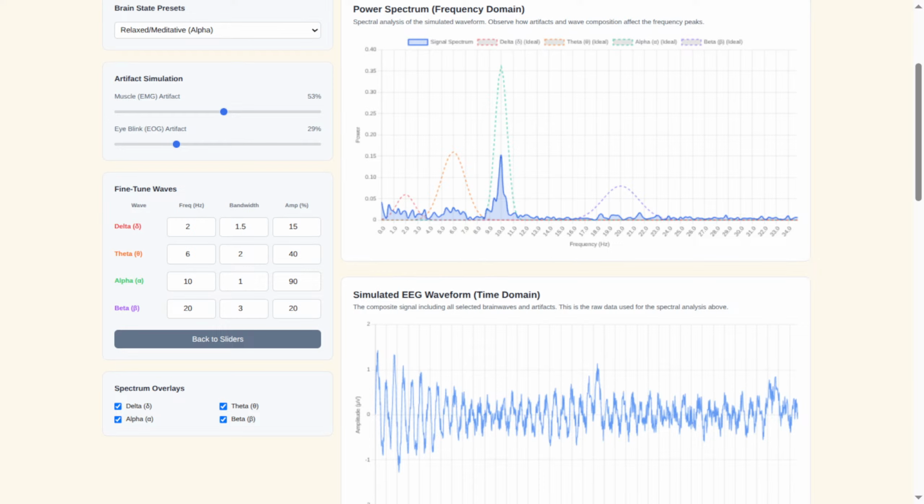Right. Then you get to the software and the algorithms. It's not just what frequency you cut off, like with the LFF. It's also about the type of filter. Is it a Butterworth filter? A Chebyshev? They sound technical, but they work slightly differently mathematically. And the filter's order, or steepness, basically how aggressively it cuts off frequencies. Different EEG software packages might implement the same setting, say LFF 1 Hz, in subtly different ways.